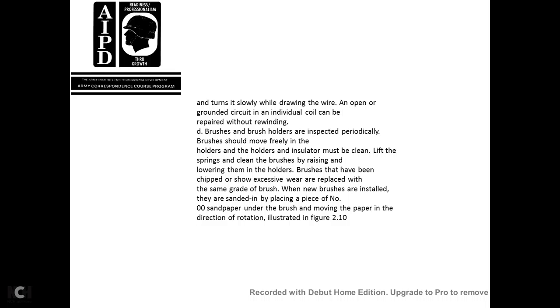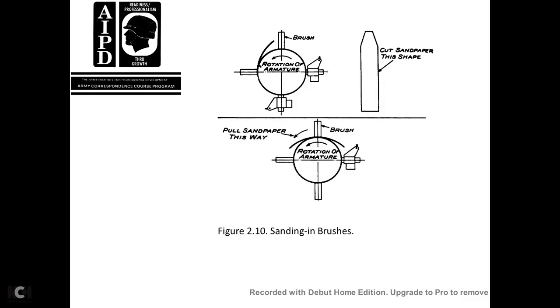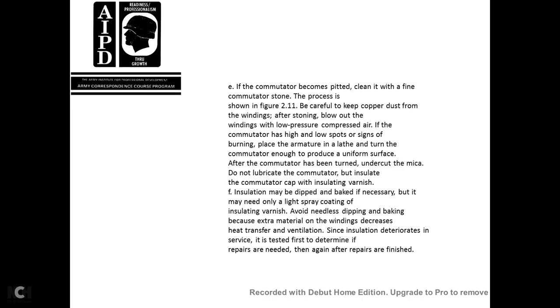When new brushes are installed, they are sanded by placing number 00 sandpaper under the brush and moving the paper in the direction of rotation, as illustrated in figure 210. Figure 210 shows the sandpaper, the brush, the rotation arrow, the cutting of the sandpaper in this shape, the pulling of the sandpaper this way, and the rotation of the armature. If the commutator becomes pitted, it is cleaned with a fine commutator stone, as shown in figure 211.